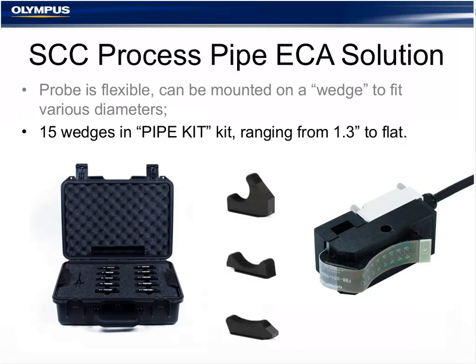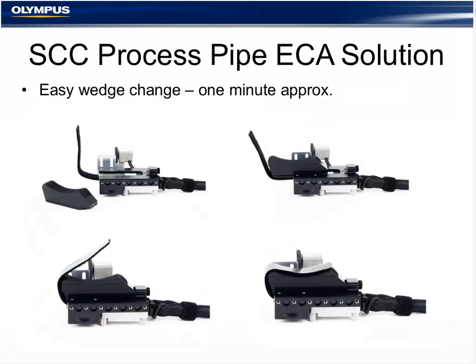So the SCC process pipe solution, the probe that comes with it, is called the pipe kit, and we offer 15 wedges just to cover any diameter from 1.3 inches, which is 33.4, I believe, millimeters, up to flat. The last wedge is 48 inches, and from 48 inches to flat, there's not enough curvature, so we decided to just go with the flat one as a large diameter. The wedges can be changed very easily. It takes about 1 minute and a roll of Teflon tape. That's not shown in the picture, but it's the most important accessory here because it prevents your probe from being damaged when scanning. So it's important to remove that tape, remove the wedge, put the new one in, and put the Teflon tape back again.